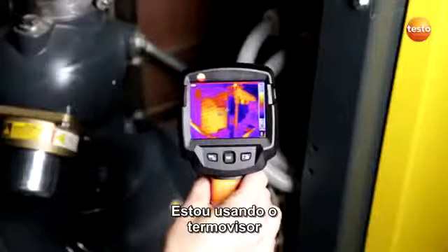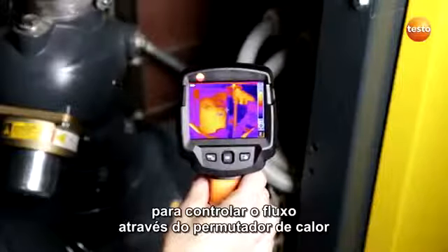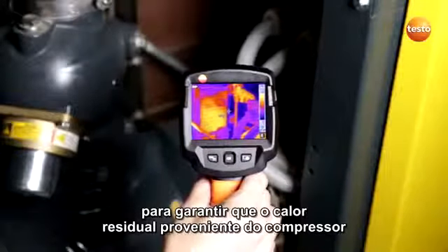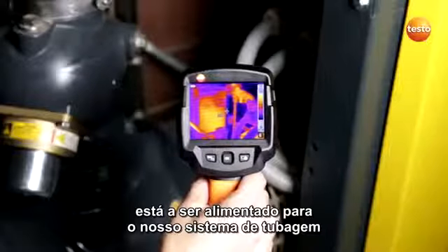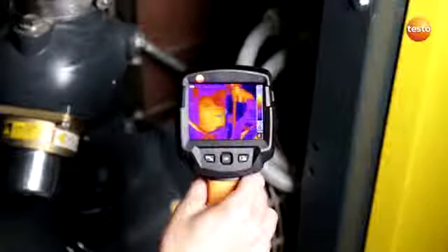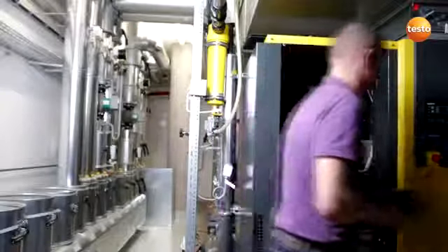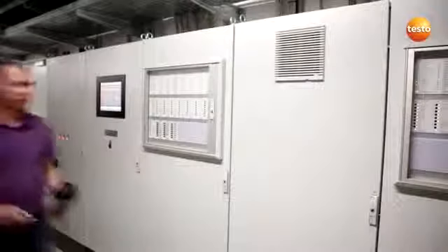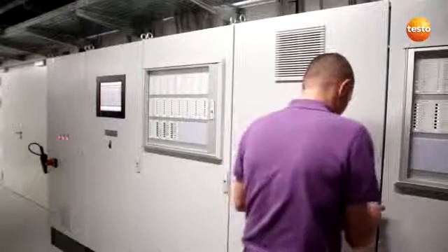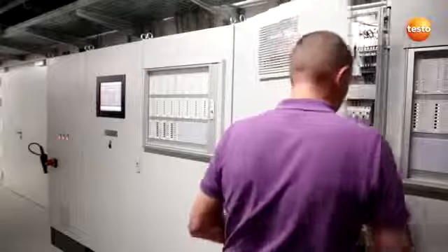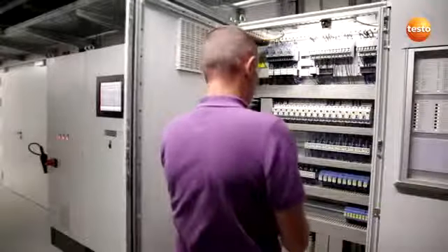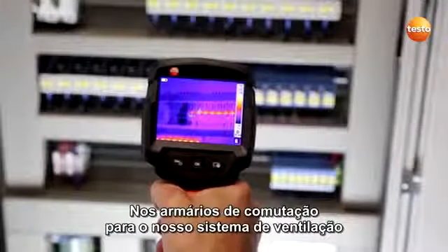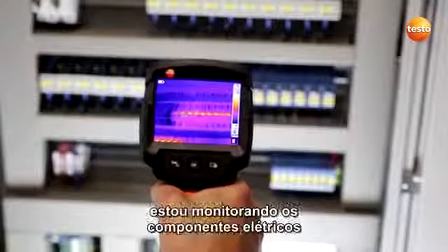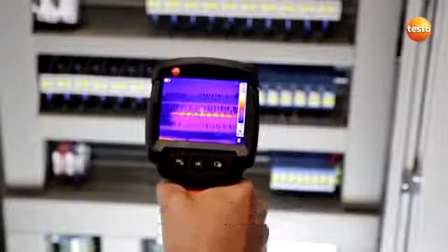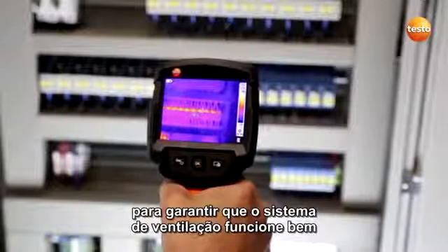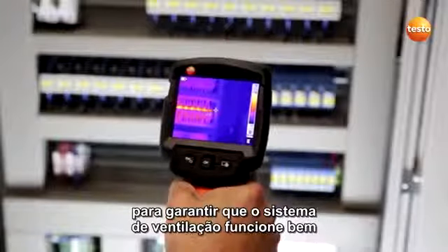I'm using the thermal imager to check the flow through the heat exchanger to ensure that the waste heat from the compressor is being fed into our pipe system. In the switching cabinets for our ventilation system, I'm checking the electrical components for temperature anomalies to make sure the ventilation system runs smoothly.